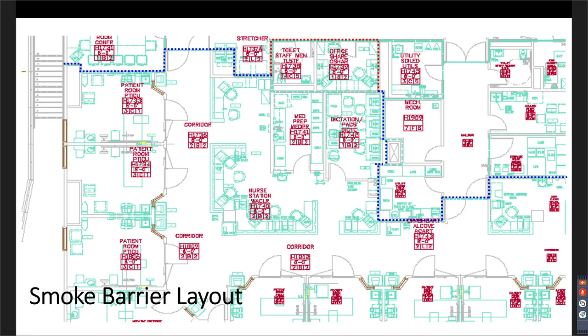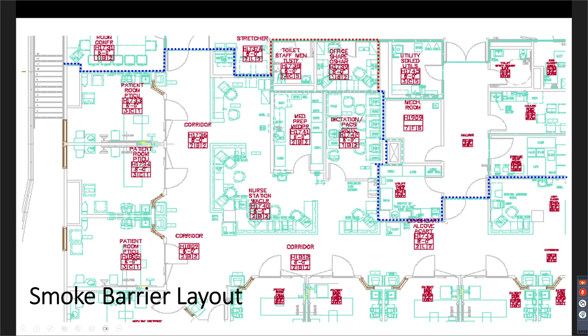So if you take a look at this slide up, pay attention up top, there's a red line where the toilet room and the office are. And you can see those doors. So the blue line is representative of smoke barrier. And that red line in this case is, but if that smoke barrier goes along that wall where the restroom and the office are, those occupants in those spaces would come out of their space into another smoke compartment and then have to go to either the left or the right to relocate and go back into that smoke compartment that they just came from. So a better design would be to bring that smoke barrier wall along the back side of those rooms so that when they leave those rooms and they're going into their own smoke compartment, and if they have to relocate, then they can go into these other smoke compartments.